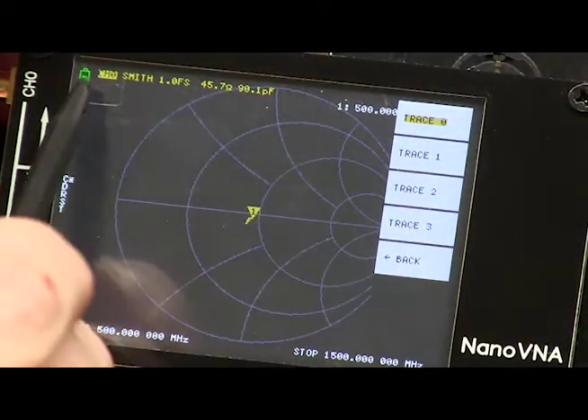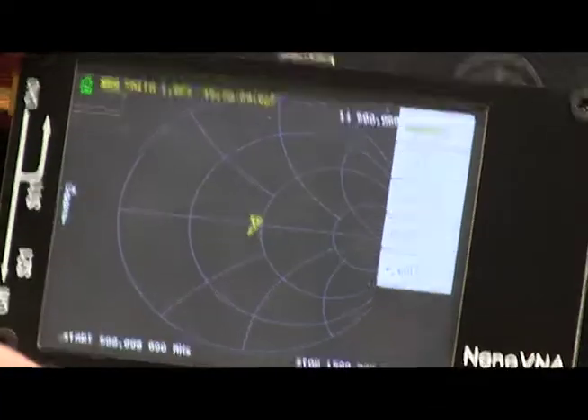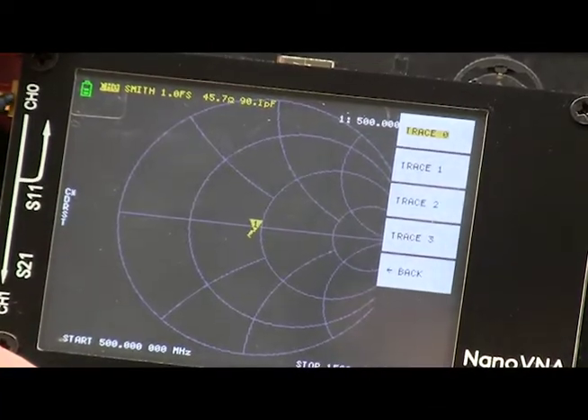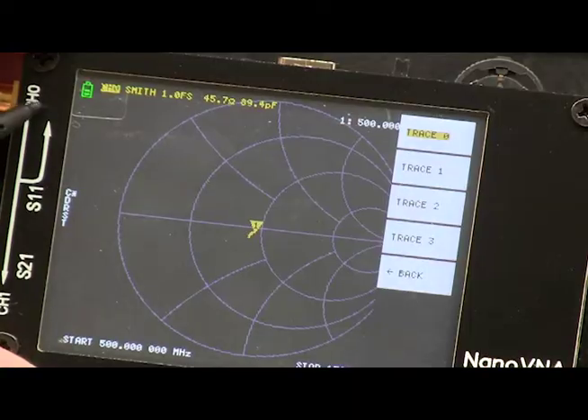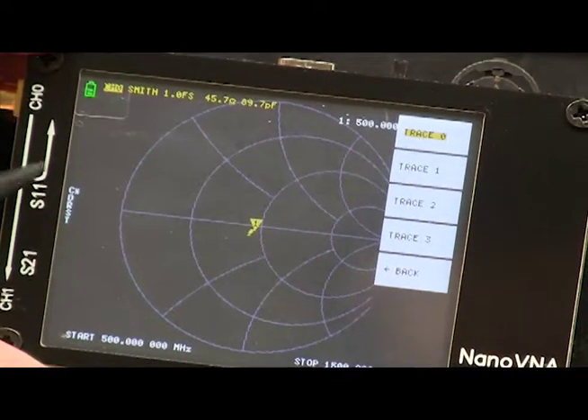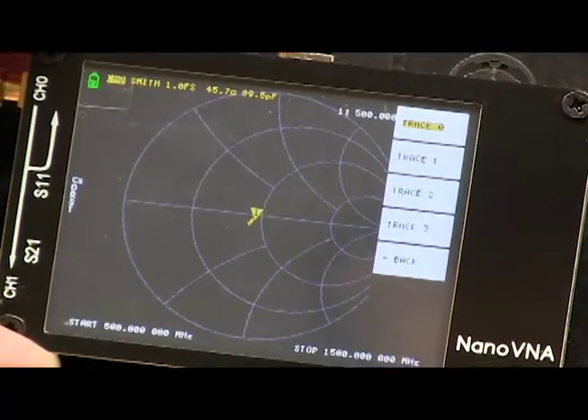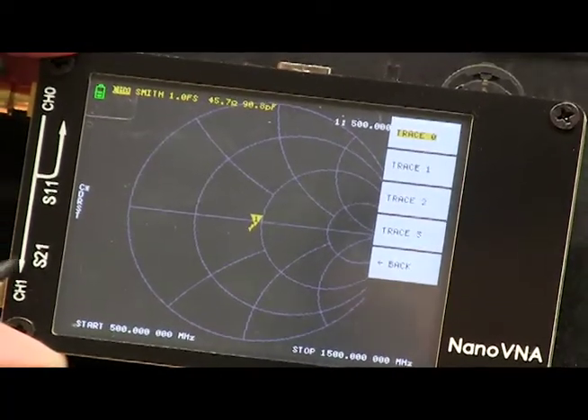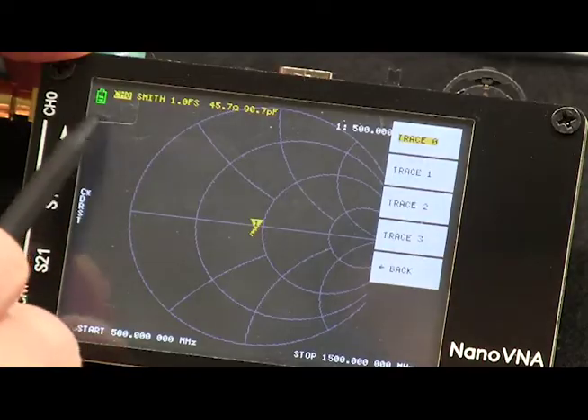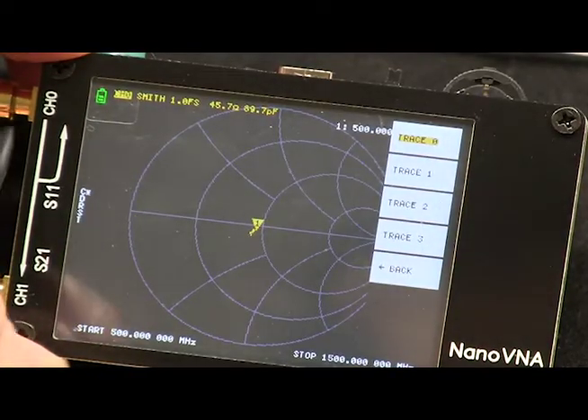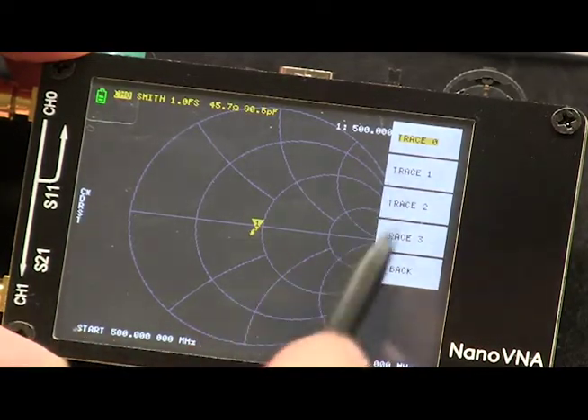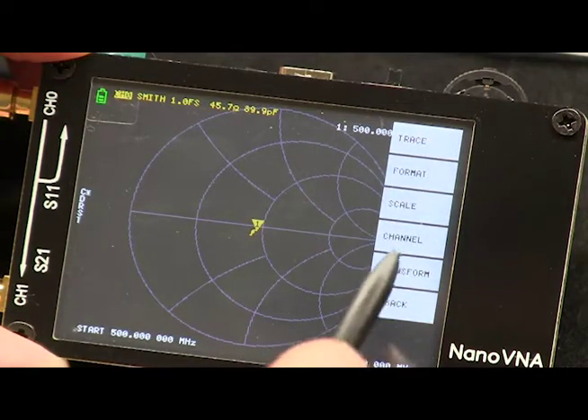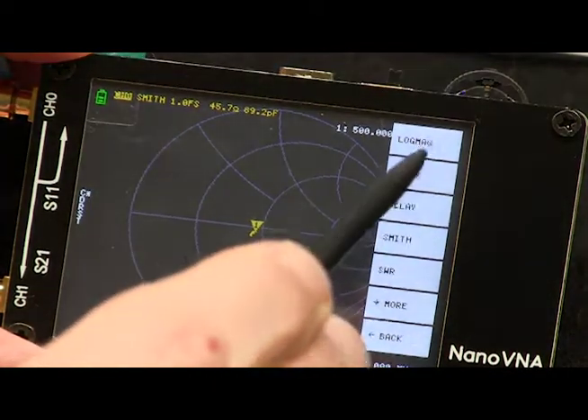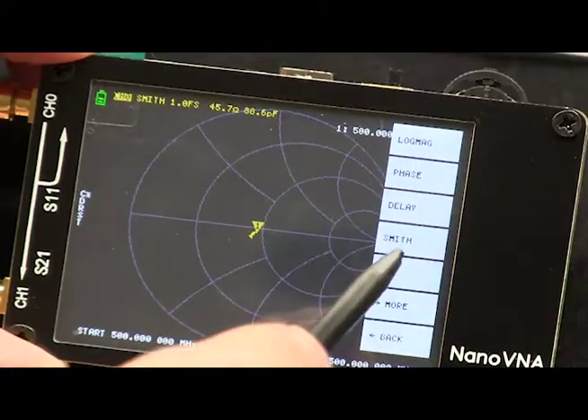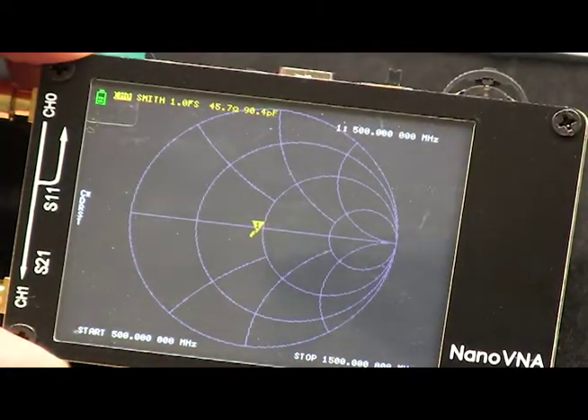The way you know what the trace is, it'll say up here channel 0, which is this channel 0. And it means S11. How do we know that? Because the only thing that's measured on CH0 is S11. The only thing measured on channel 1 is S21. So it says CH0, so I know it's measuring the reflection S11. And now that I know I'm measuring S11, I can go to the format and I can click Smith, and that's what I get right here.